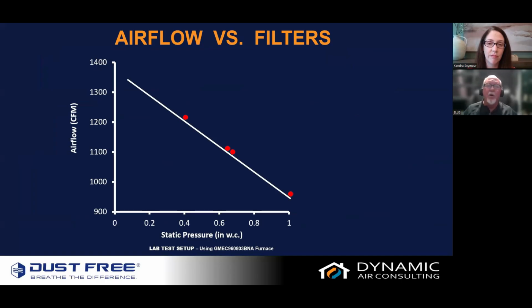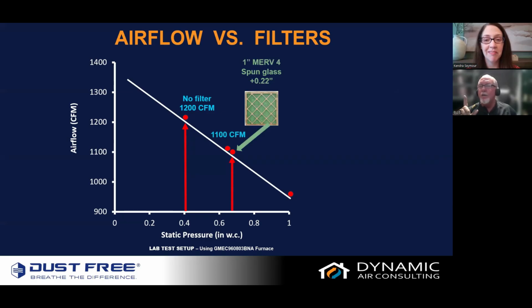With no filter in it whatsoever, we're able to move 1200 CFM right on the dot. So we're going to introduce a 1-inch MERV 4 spun glass. Its static resistance is 0.22. We've already lost 100 CFM. Now, it's only a MERV 4, which is better than a MERV 0, and we're going to talk about MERV in a minute. But I want you to understand this is made out of spun glass. Remember, I talked about some of the things that filters are made out of.